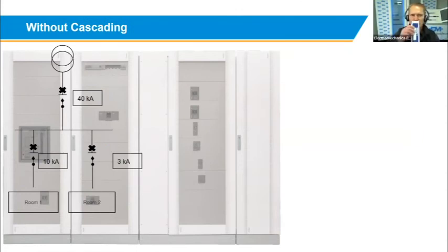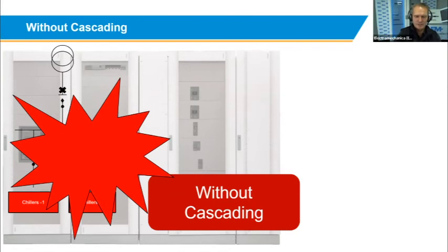In scenario 2, somebody worked there and by accident did not look at the breaker they're replacing, and they took a 10 kA product out and replaced it with a 3 kA product, maybe from the same manufacturer. The problem with this is that this installation or this method of cascading was not tested. So what could happen is when a short circuit appears, again in this circuit here, the circuit will open, and this 3 kA product will not be able to handle the 40,000 amps that the board is rated for. And what will happen is that you may have a huge explosion in your installation and cause a lot of damage.